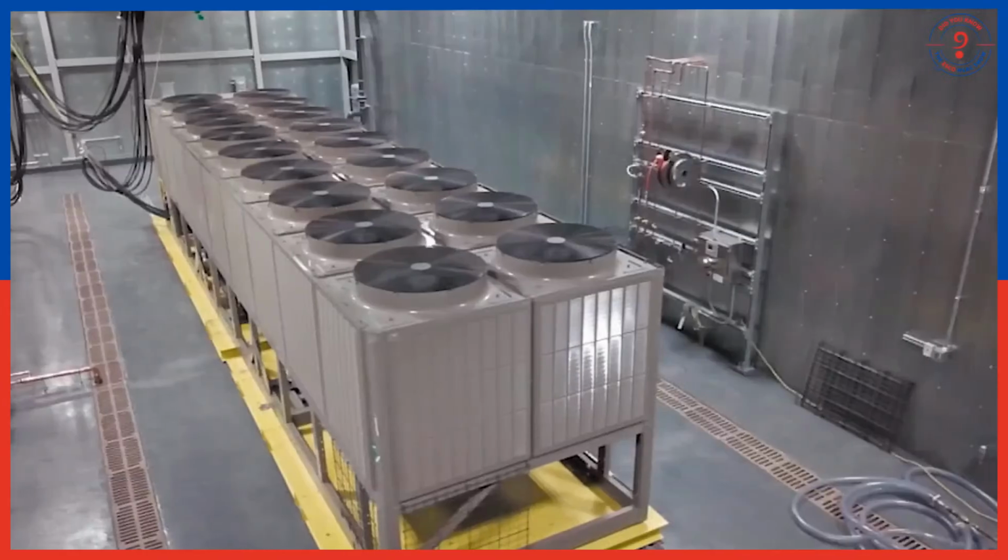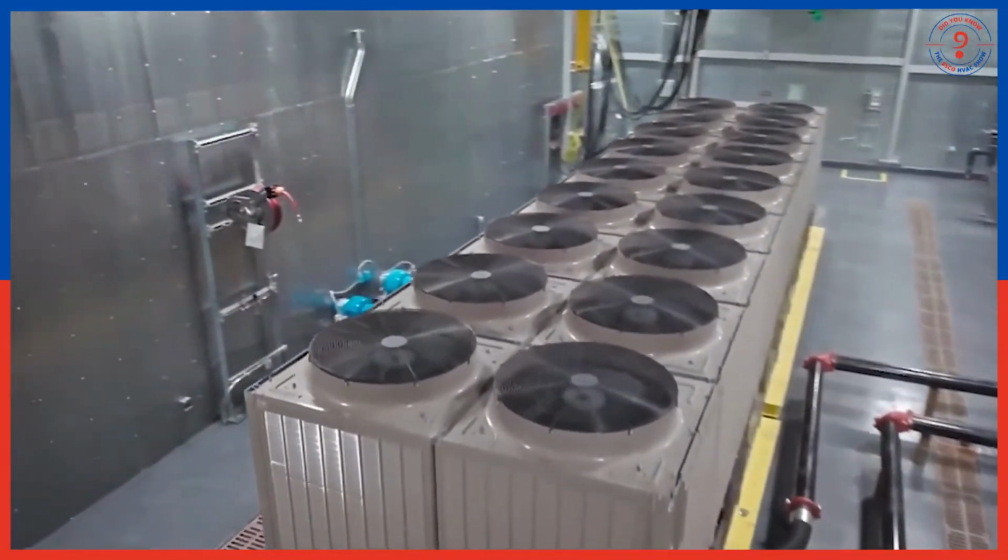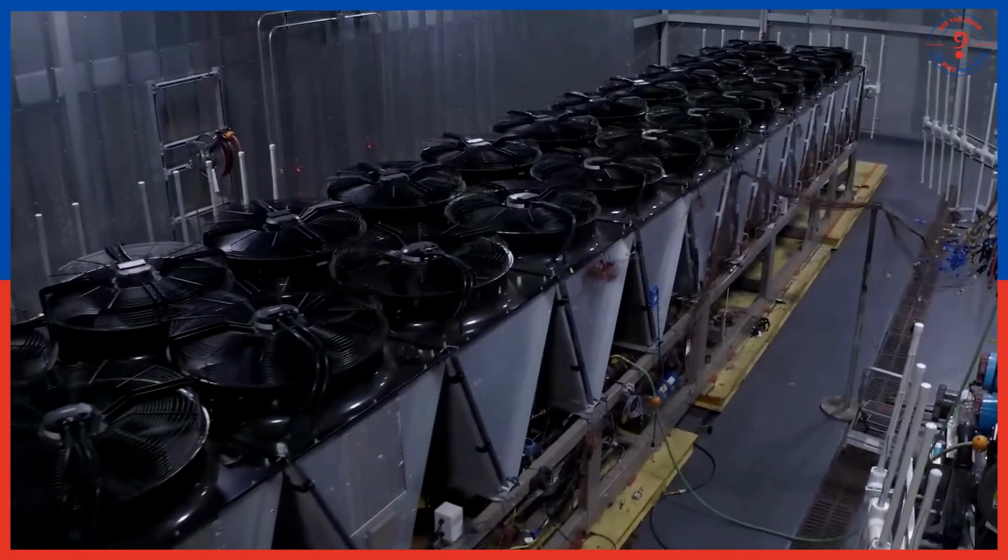You know, we hear a lot about the equipment that's being manufactured by Johnson Controls, and how so much of it is truly manufactured by Johnson Controls, designed and engineered in-house. And then when you bring it into these facilities, we're testing in conditions I'm hearing down to like minus 20 and up to what, 131 degrees Fahrenheit, something like that? That's correct. So we can actually put those pieces of equipment in those environments and see how they function. Absolutely. Another great feature here is because of the features of our facility, we can place a chiller on a test facility at certain conditions for extended periods of time to ensure the reliability and longevity of it before it gets to the customer. So these are the advantages we have with our test facility.